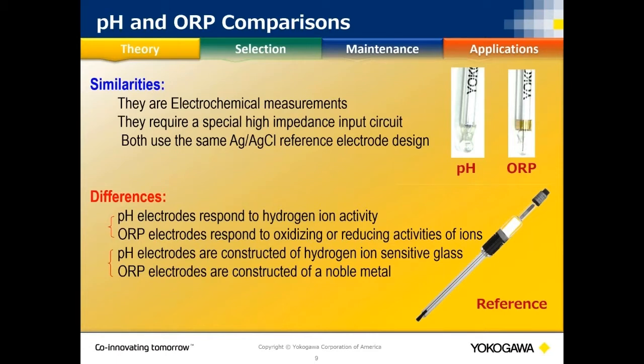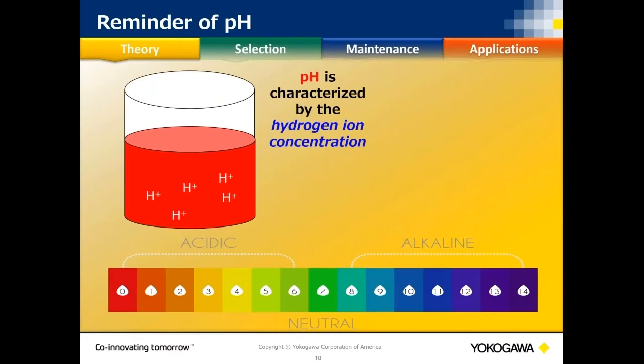What's similar and different about pH and ORP? You'll use the same silver silver chloride reference for both, so any problems with pH — coating and plugging — you can expect with ORP. Both are electrochemical measurements. With pH you have a glass membrane that reacts only to hydrogen. ORP uses a noble metal, either platinum or gold, and it reacts to anything oxidizing or reducing in your process, including hydrogen ion activity.